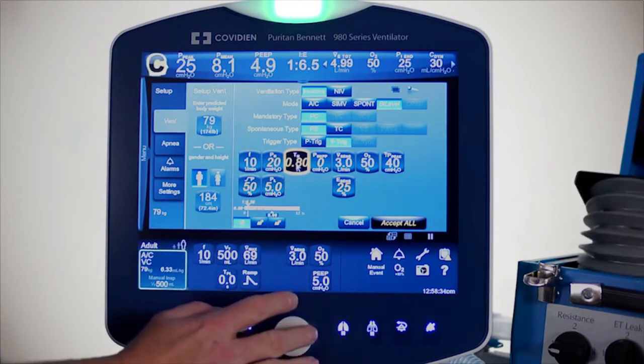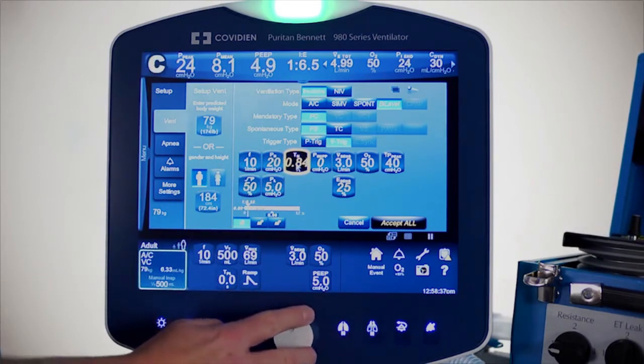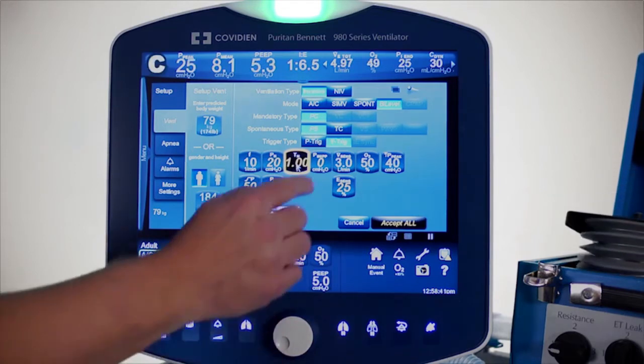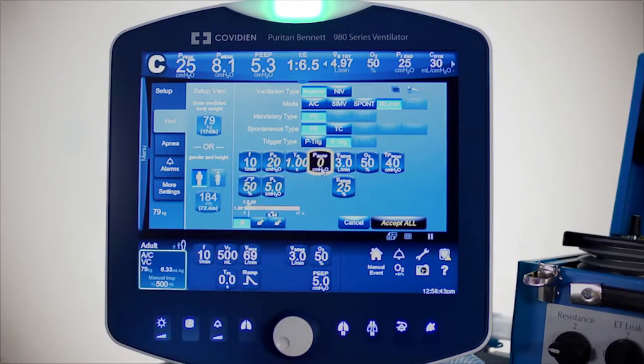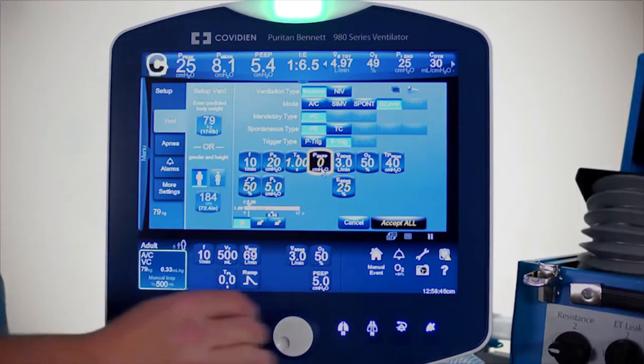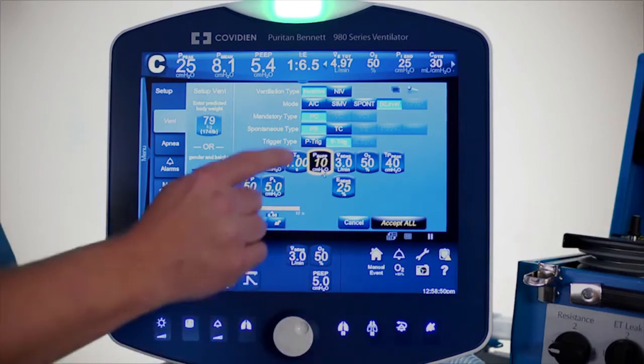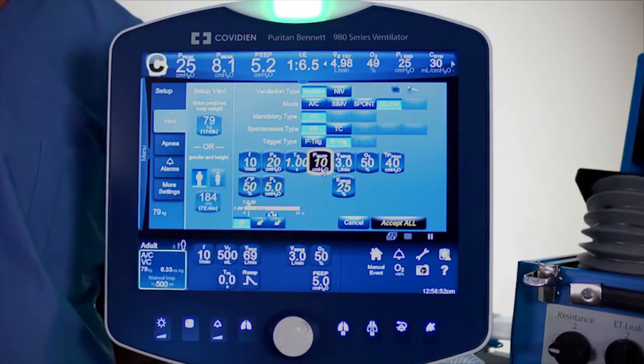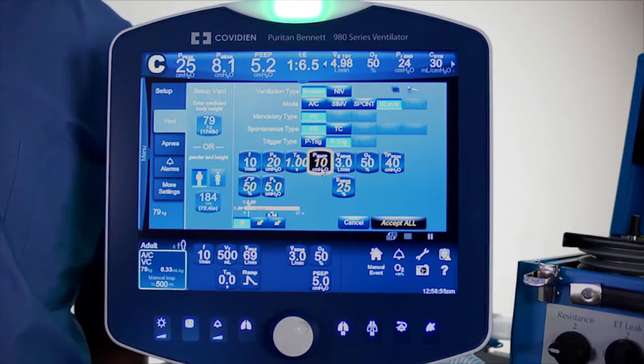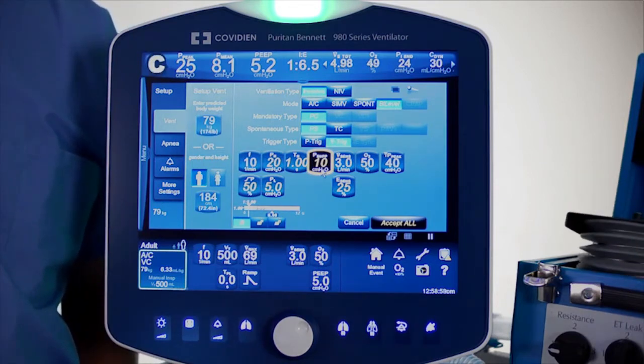The next variable is the time spent at high — some people may call it inspiratory time. I'll put this at one second for now. For pressure support, because this is an SIMV strategy, I'll put in pressure support of 10. That pressure support is on top of PEEP, so if I have 5 of the low pressure plus 10 of pressure support, that's a total of 15.